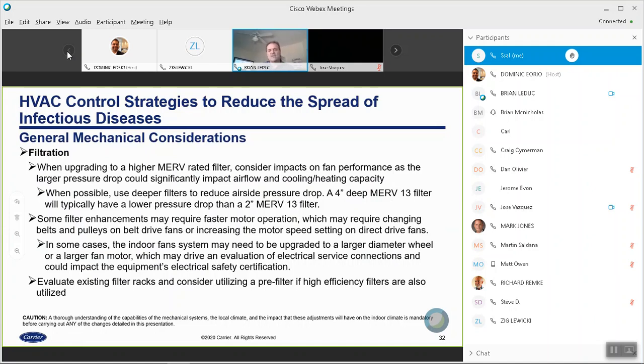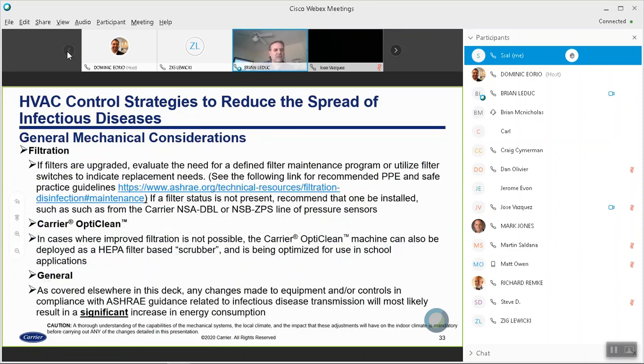Again, you might have to increase the speed of the fan if you do a significant increase in pressure. And again, evaluate the filter racks. Consider additional filtration if possible. Again, these are things that could potentially be difficult to achieve. Again, I mentioned safety in terms of your filter maintenance program. This is a new piece of information that was just provided to me yesterday.